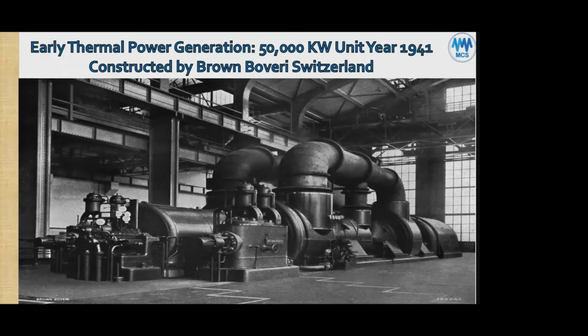So I brought up this picture to show an example of how steam turbines and gas turbines, of course, are related to heat. They require heat to operate. You can't run them with cold steam or cold water. Well, hydro turbines you can with cold water, but steam turbines require hot steam. So high temperatures introduce thermal problems. They introduce thermal transient expansions in the casings, in the piping, and in the rotor itself. And this is a 50,000 kilowatt turbine train.